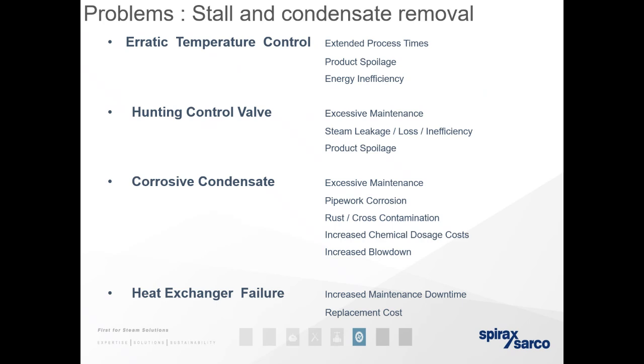So the things that you may start seeing on site, that are an indication of stall, is erratic temperature control. So your process times are taking longer to heat up. Spoilage, so for instance, if we talk about the dairy industry, if products do not achieve temperature for pasteurization, most of the time that product has to be wasted. And then there's investigations on why that was wasted. Energy inefficiency. So the more stall, the more condensate you have in your system, the less energy efficient it's becoming, which means it's becoming more expensive to run.